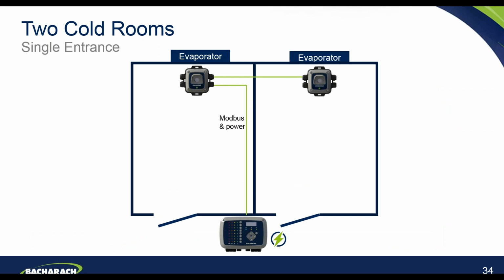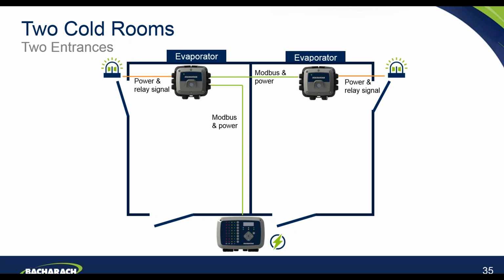In this example, you have 2 cold rooms together. So you have a 408 control panel which sits in between the entrance to each of those rooms. Again, the power supply is to the control panel, and then that control panel powers and interfaces via Modbus to the 2 detectors, one in each of those rooms. So again, you have audible visual notification inside the room, outside the room also with the control panel, and you have a very simple Modbus and power connection daisy chain there to make that an easy and simple installation. If you had additional entrances to those rooms, again, you can drive power and relay signals from the MGS-450s in each of those rooms to drive an additional beacon sounder which sits outside.